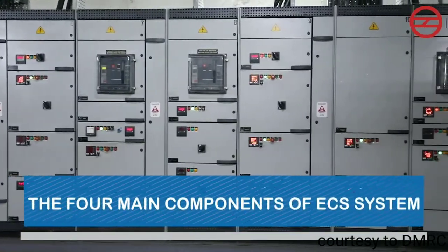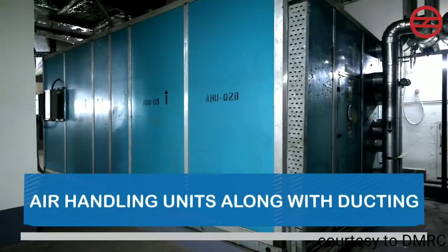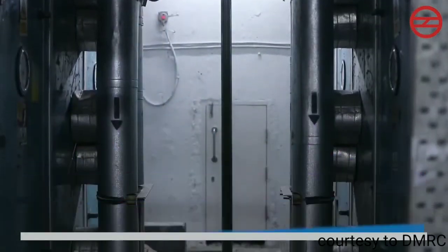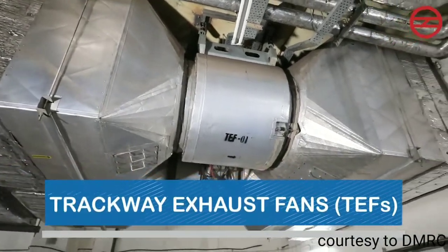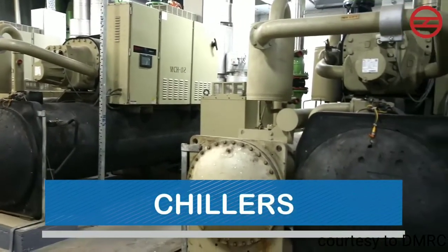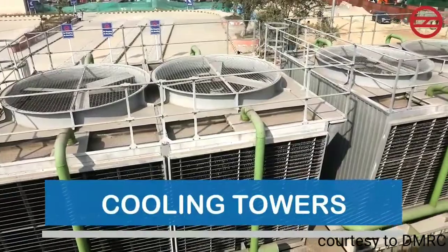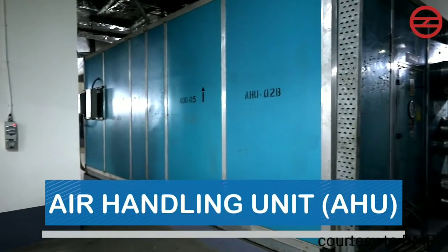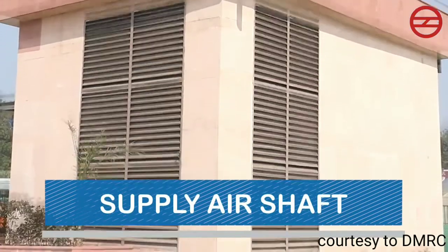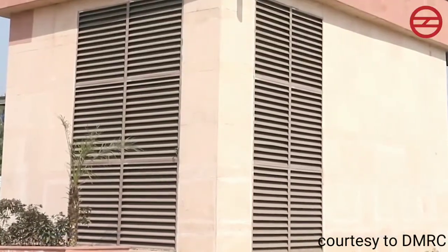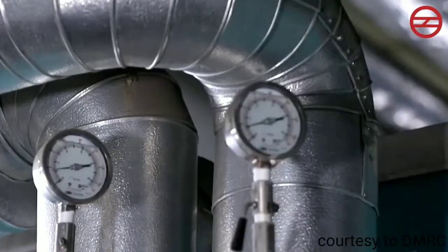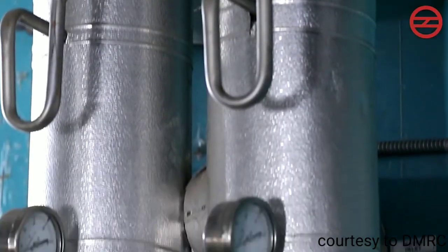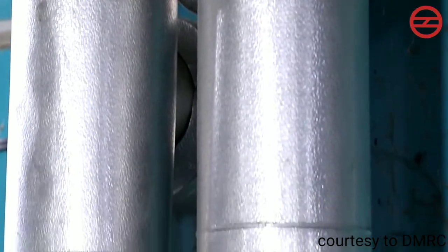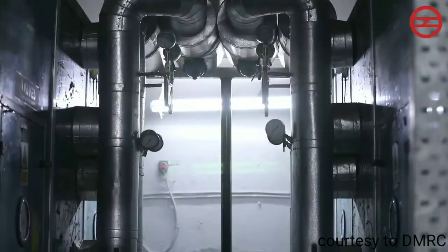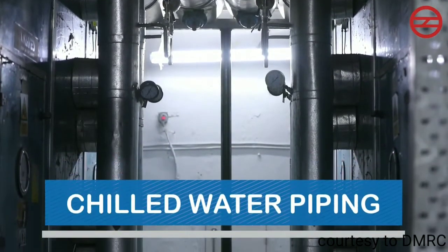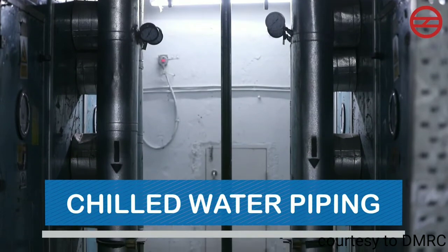The four main components of ECS systems are air handling units along with ducting, trackway exhaust fans, that is TEFs, chillers, and cooling towers. Let's talk about air handling units. These are connected to a supply air shaft and have a blower and cooling coils. The blower is used to supply the air which is passed over the coils carrying chilled water. This cool air is then circulated in the entire public area with the help of ducts and grills. In winter season, there is no supply of chilled water and AHUs simply supply outside fresh air inside the station.